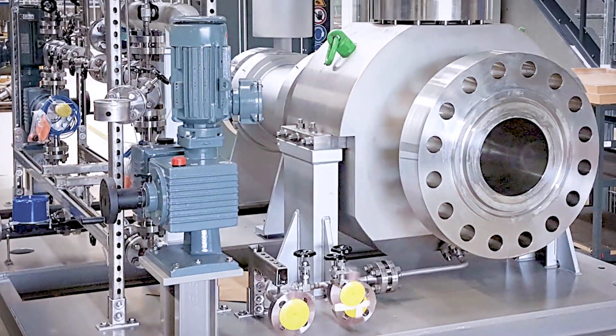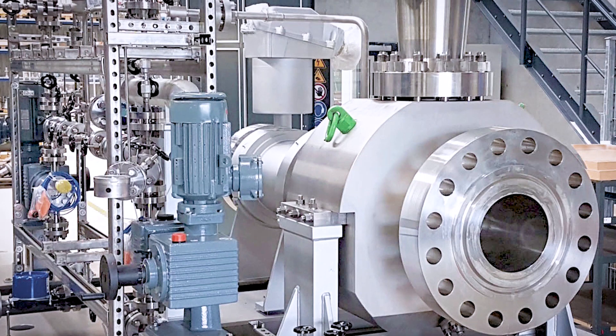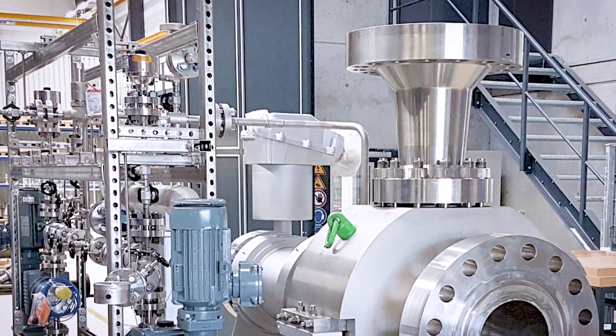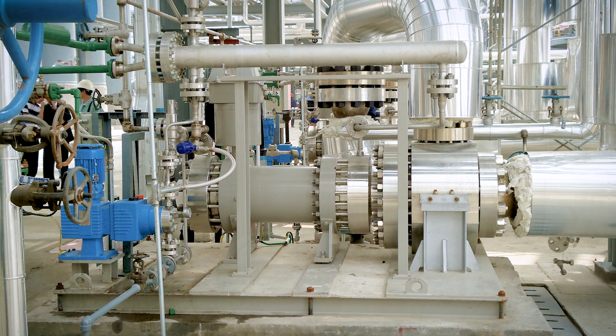Of course, we do not only deliver to the chemical and refrigeration industry, but also to the oil and gas industry, which is a very important industry for us. As an example, what you see here is a pump in a diesel fuel desulfurization plant with a capacity of 1000 cubic meters per hour, a delivery head of 65 meters, and a system pressure of 112 bars. The operating temperature at this application is 405 degrees and the design is according to API standards.